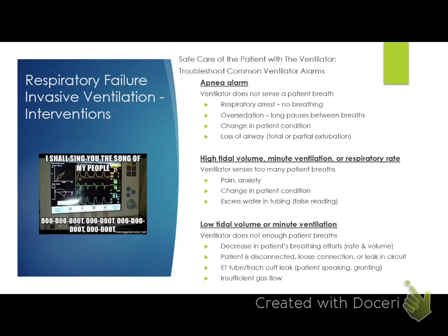There's high tidal volume, high minute ventilation. This is where the ventilator is set to give a certain amount of air with each breath or monitor a certain amount of air in and out. So if the patient starts breathing at a respiratory rate of 30, they're moving a lot of air per minute, and that might be something that sets off an alarm. Or the patient doesn't breathe enough, which might set off the alarm.